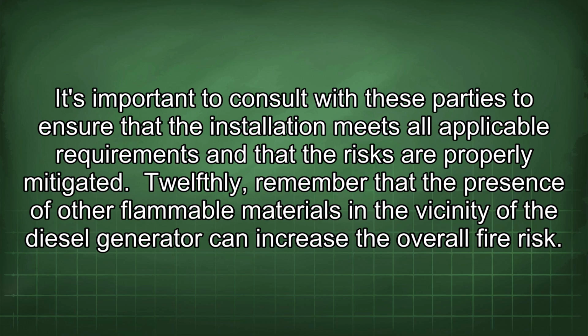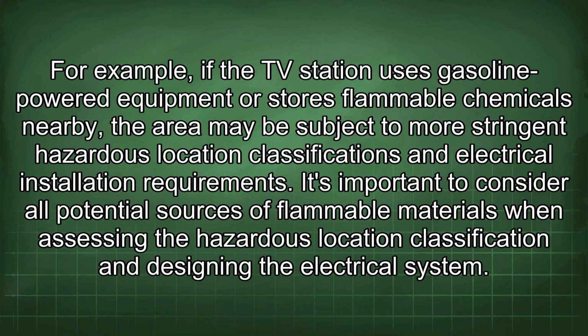are properly mitigated. 12thly, remember that the presence of other flammable materials in the vicinity of the diesel generator can increase the overall fire risk. For example, if the TV station uses gasoline-powered equipment or stores flammable chemicals nearby, the area may be subject to more stringent hazardous location classifications and electrical installation requirements.